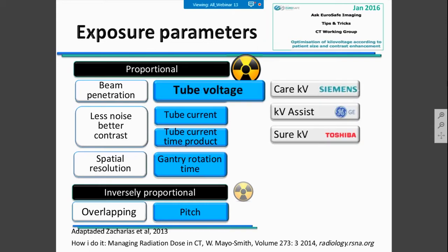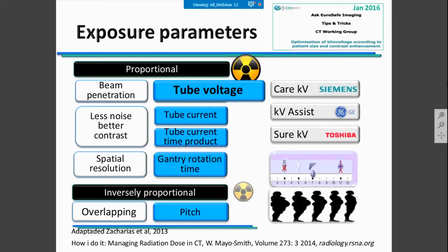To help us, some new tools have been developed in our CT scanners. For example, tube voltage modulation—it may have different names from different manufacturers, but at the end, the goal is to decrease dose. These tools are based on patient size and also on the clinical indication. You could have lower examination dose values if you have this tool in your CT scanner. However, if you don't have it, you can reduce the tube voltage in some procedures that you normally perform at 120 kV.